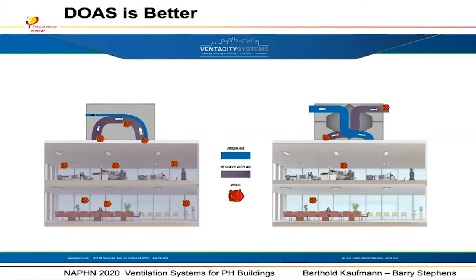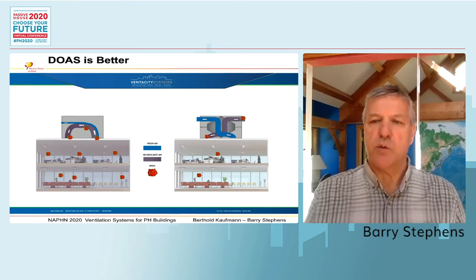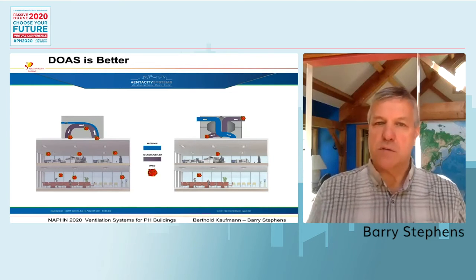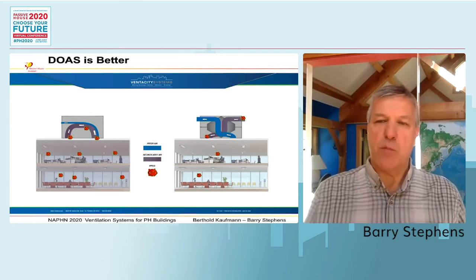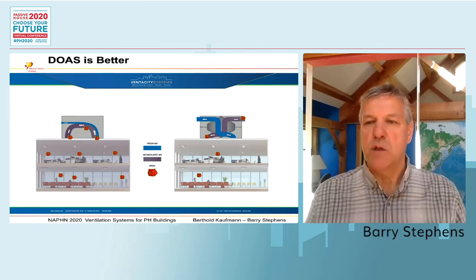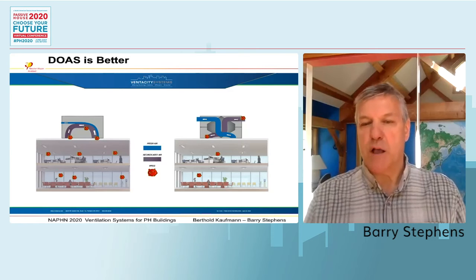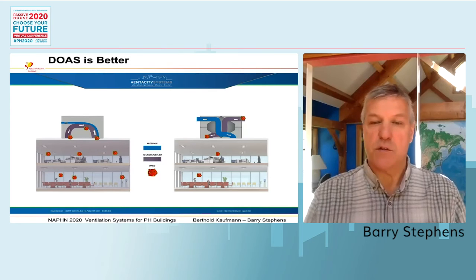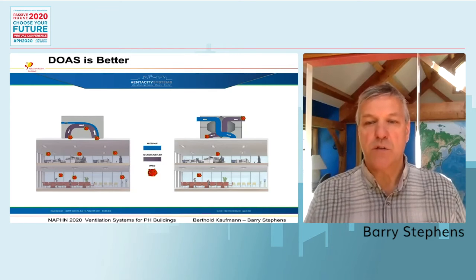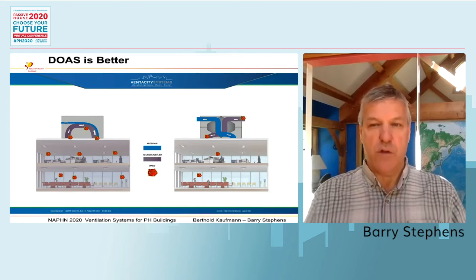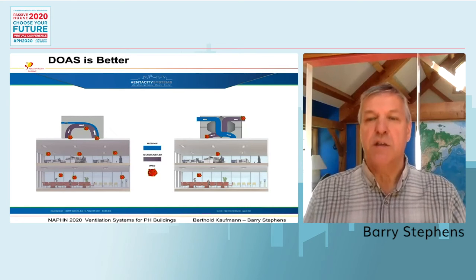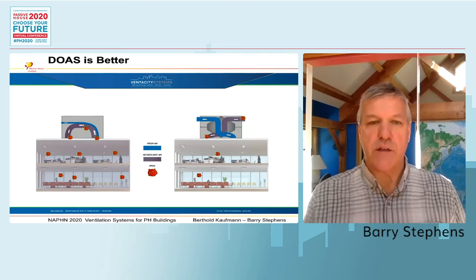We talked earlier about the cross-flow contamination limits that Passive House has, and they test those at static pressure differential. In other words, positive pressure on one side and negative pressure on the other, so that you're not seeing any contaminated air pushed across into the supply air stream. That eliminates the possibility of cross-flow contamination and having viruses spread back into a building. So this is very, very critical. And the Passive House certified products are tested to not have any of that leakage.